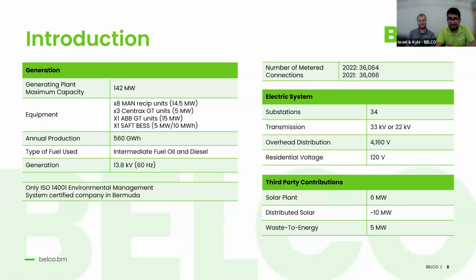In terms of an introduction, a little bit more of the details. In terms of the generation side, plant capacity nameplate is about 142 megawatts. The equipment that we use is 8 MAN reciprocating units. So those are 4-stroke engines. They're about 14.5 megawatts each. We also have 3 Centrax gas turbine units. Those are aeroderivative units, about 5 megawatts each. We also have 1 ABB gas turbine unit. That's an industrial frame unit that does about 15 megawatts.